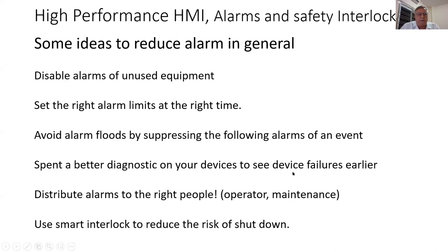Then spend better diagnostics on your devices. Many devices can deliver a lot of diagnostic values, and so they can tell you that they need some maintenance. The other is to distribute the alarms. Let it not all be done by the operator. Some alarms are more interesting for maintenance, others for the operator, for the process. And then use smart interlocks to reduce trips. That is what I mean, if the DCS should also support in the back end.